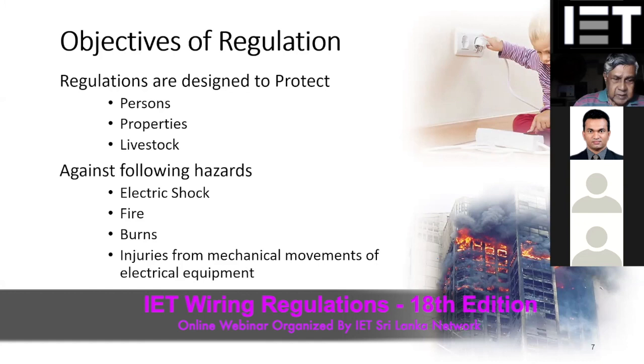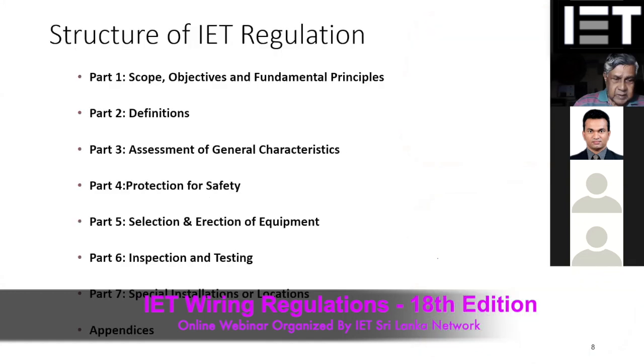Now, when you look at this IET wiring regulation, it is structured in a certain manner, where there are part numbers. Normally in a book you have chapters at the topmost layer, but in the regulation what we have is a part. There are 7 parts in the regulation. If you look at the 16th edition and the previous ones, special installations were under part 6, and inspection and testing was under part 7. But from the 17th edition onwards, this was changed: special installations are listed in part 7, and inspection and testing is listed under part 6.